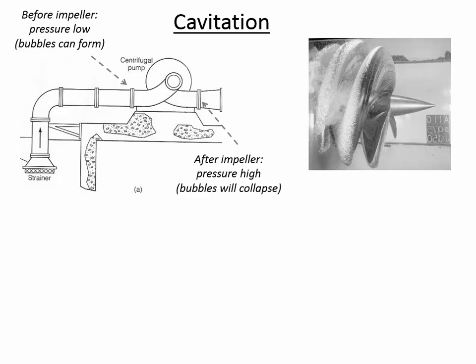Okay, cavitation is a risk when the pump is too high above the origin reservoir, or if you have a really long suction pipe, or if the suction pipe has too small of a diameter. Any of those 3 things is going to increase the risk that the water pressure gets really low before you get to the pump. So remember that what we said was the water pressure here is 0 since we're at the same elevation as the liquid.